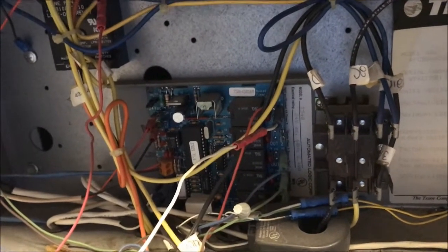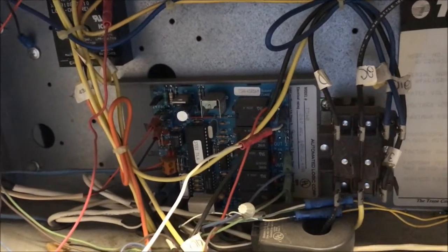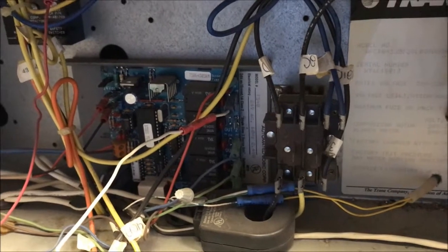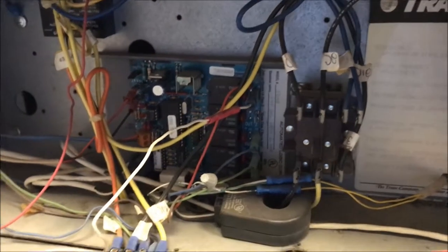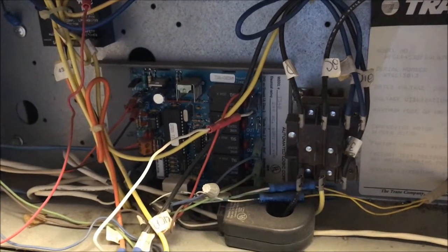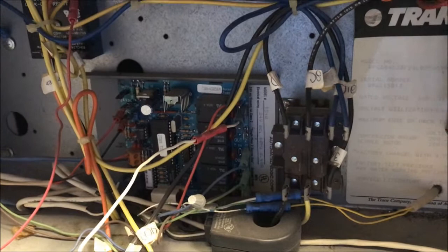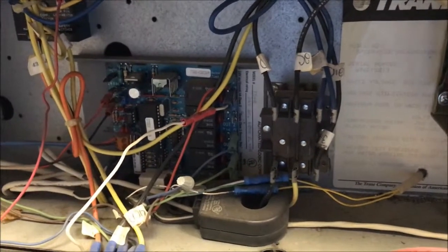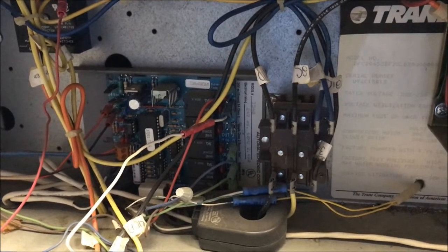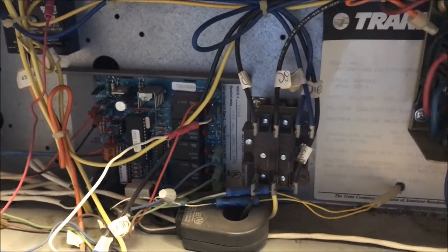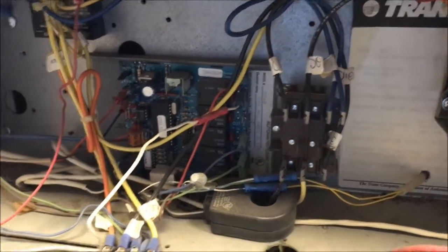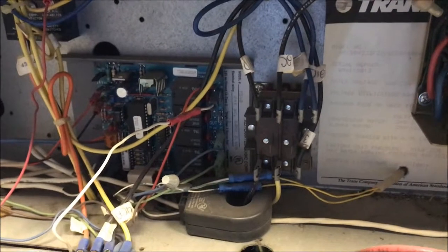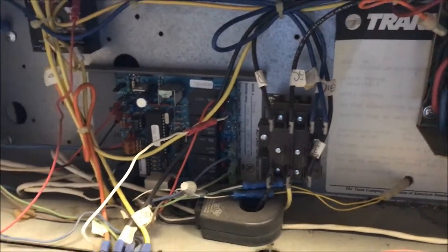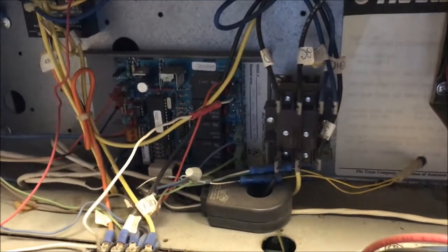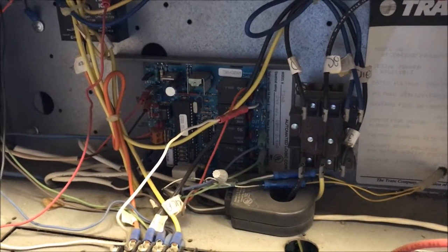There's probably about 25 or 30 units on this loop. I'll shut all those off, then go to the boiler and shut it off at the boiler control. Then we're going to valve off and isolate the section where both pumps sit, open it up, drain that section out, raise the pump up and put it back in place. Then I'll wire it in, verify rotation, and get the system back up. After that I'll go back through and turn all these units back on, and they'll start heating up since it's cold outside and they're pretty much in heat mode right now. Get it all back up and going. So let me get to it.